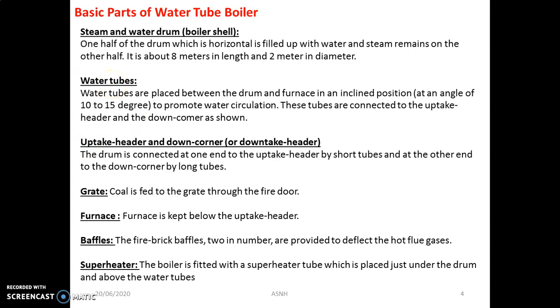The uptake and downtake headers are there to continuously circulate water in the drum. The grate is the passage where the actual fuel, like coal, is burned. The furnace is the area above the grate where combustion of fuel takes place and hot flue gases are produced. Fire brick baffles, approximately 2 in number, are provided to deflect the hot flue gases for separation purposes. The boiler is fitted with superheater tubes placed just under the drum and above the water tubes, whose main function is to increase the temperature and pressure of the steam generated.